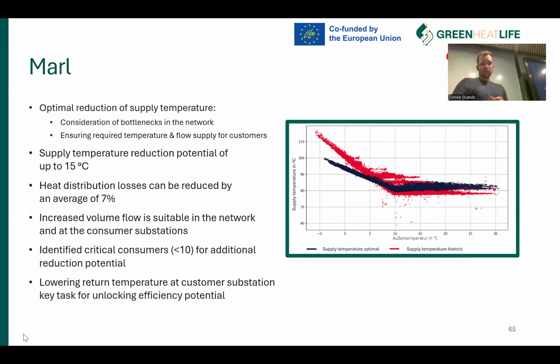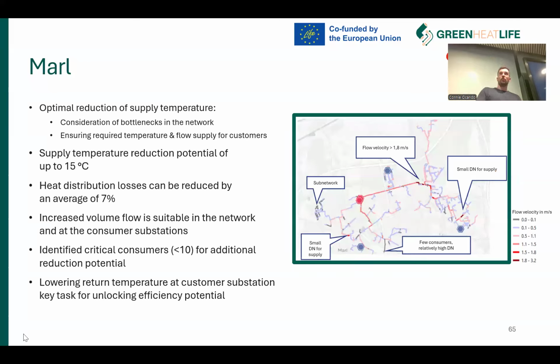As I mentioned, the volume flows will increase, so we also have an evaluation for the network here. The digital twin showed us where we have bottlenecks or where critical points may arise with higher volume flows. You see here in the east middle of the network, one pipe reaching 1.8 meters per second. It's still beneath the threshold of 2 meters per second, but we know this area of the network could become critical if we further reduce the temperature or add additional consumers to the eastern part of the network. We also know which other areas might be critical for the decrease of supply temperature. So it's very good experience we get here from the digital twin.